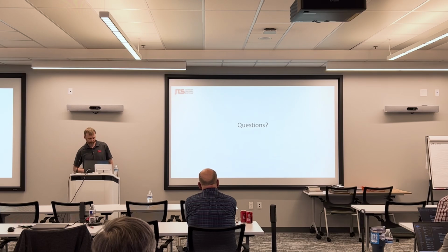Air evaporators may frost at warmer temperatures. Glycol chillers may need higher concentrations of antifreeze. Only charge with blended refrigerants. Calculate superheat based upon dew point. Calculate subcooling based upon bubble point. And then it's recommended to have lab sample analysis of your refrigerant after multiple leaks, or to reclaim and recharge with virgin refrigerant. Questions?